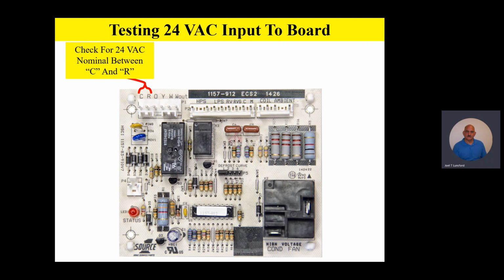But the very, very most important is probably to make sure when you're doing sensor checks that you've got 24 volts to the board all the time. Now, this has to be year-round. It doesn't matter if it's summer, fall, or winter, or whatever the case may be. You have to have 24 volts on this board all the time between C and R. Now, if you don't have 24 volts on the board, repair it and figure out why you don't have 24 volts on this board all the time.